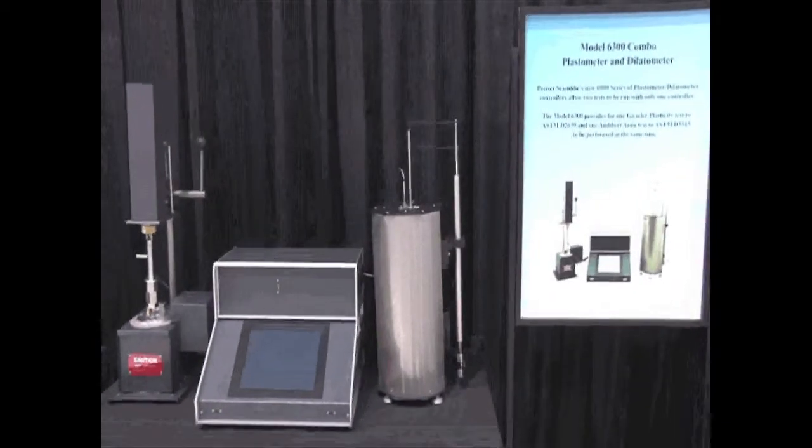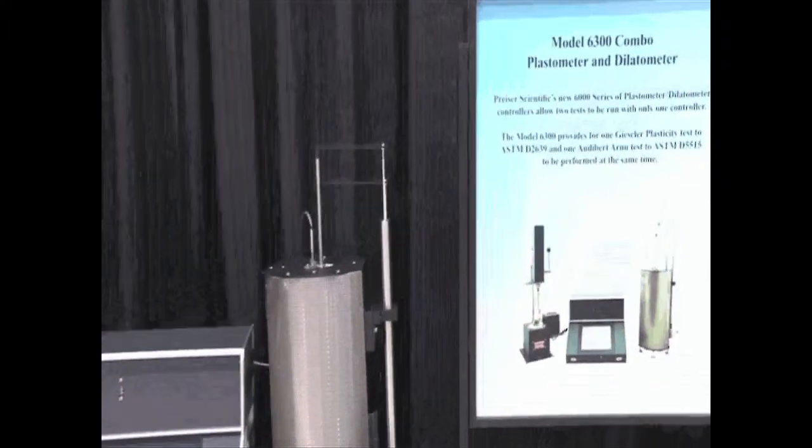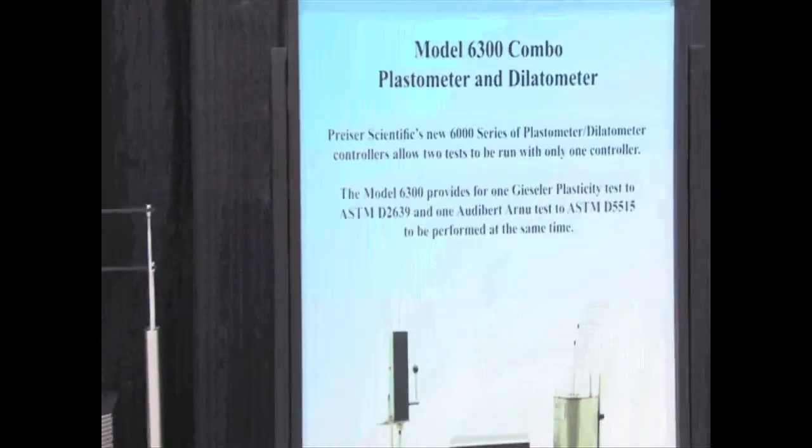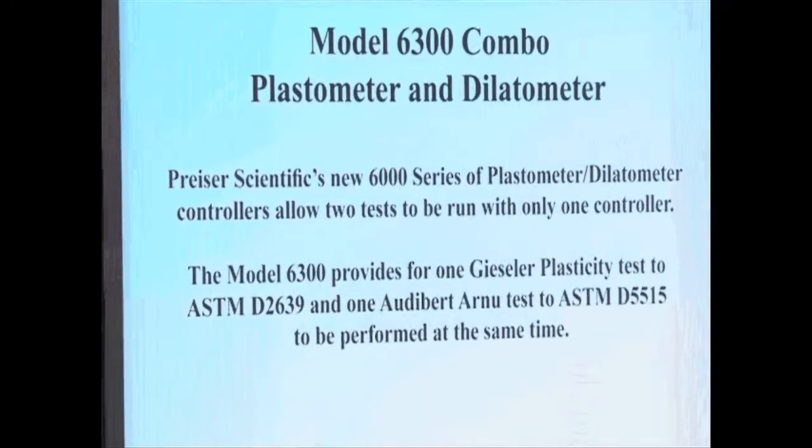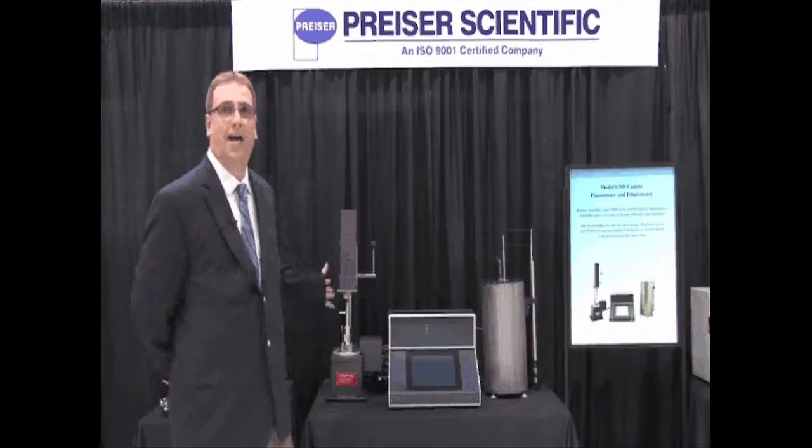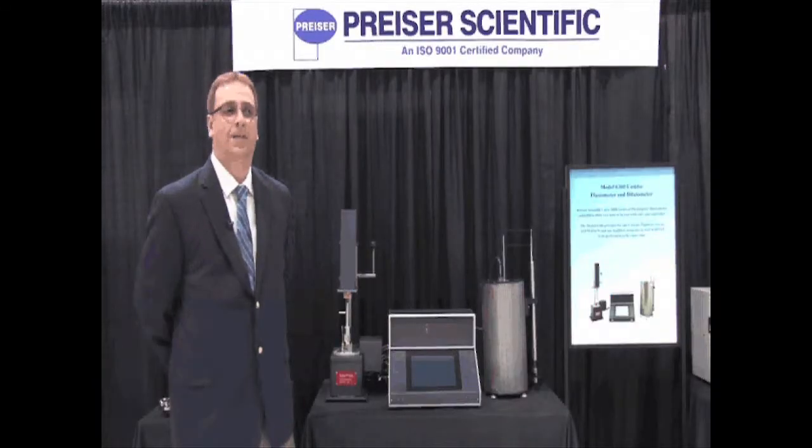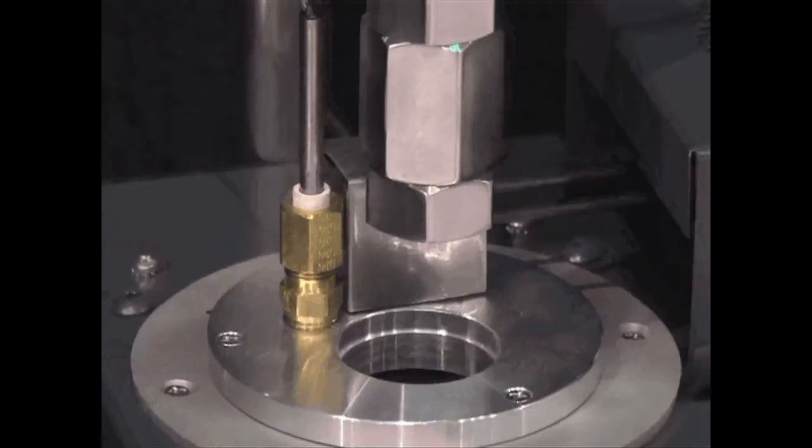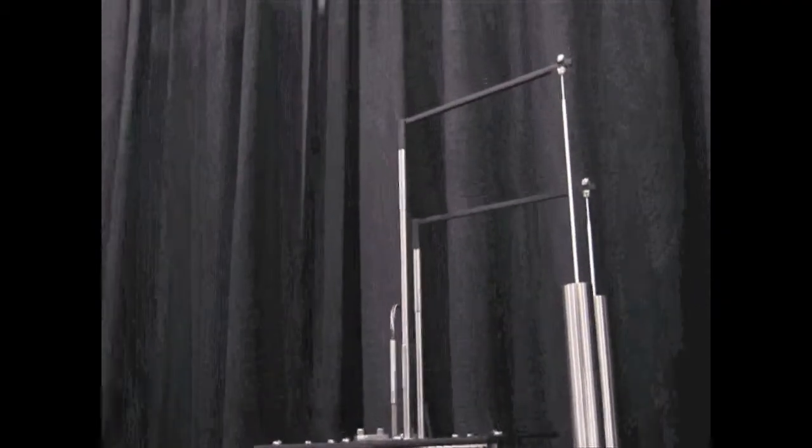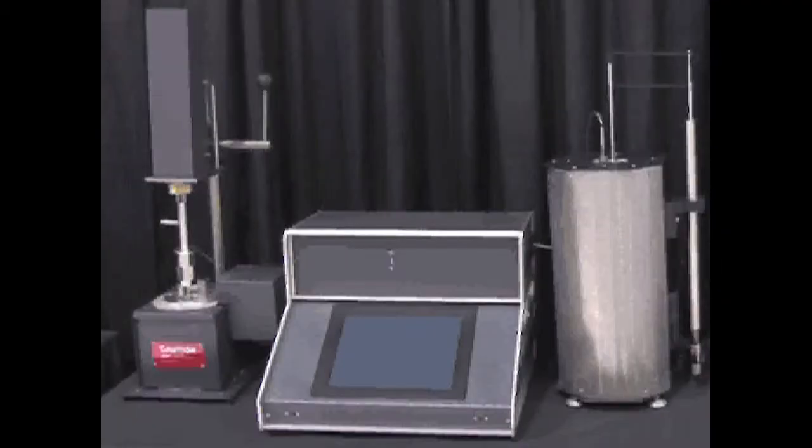The positive feature and benefit of this unit is you can configure it in many different ways. This unit here is actually our combination unit which has one dilatometer and one plastometer furnace on it. You can also get this configured as one plastometer or one dilatometer, or actually dual systems of both - two dilatometers or two plastometers.